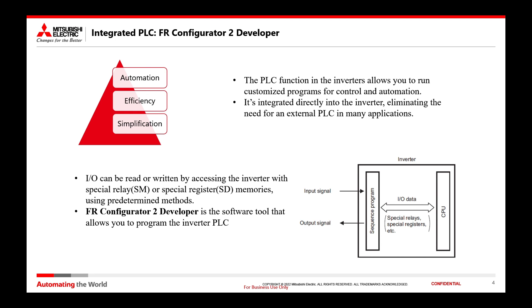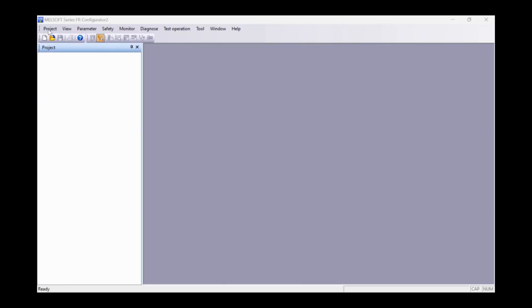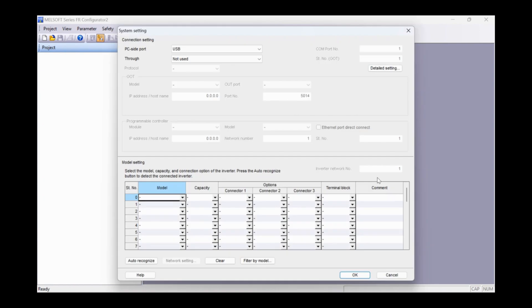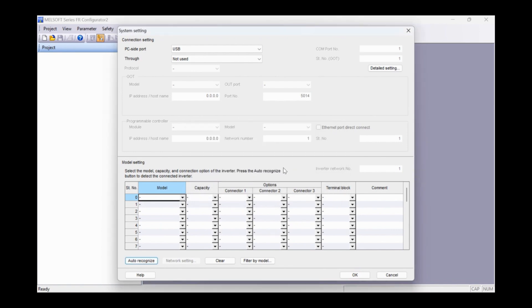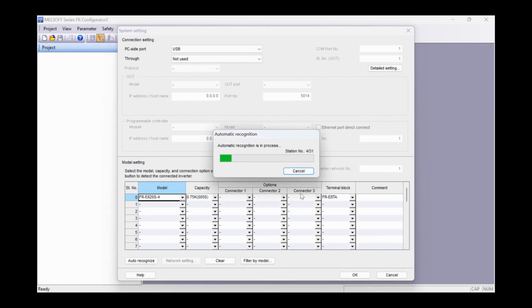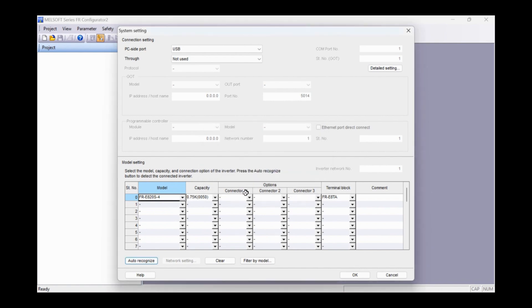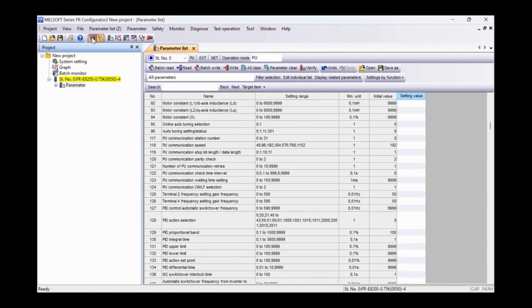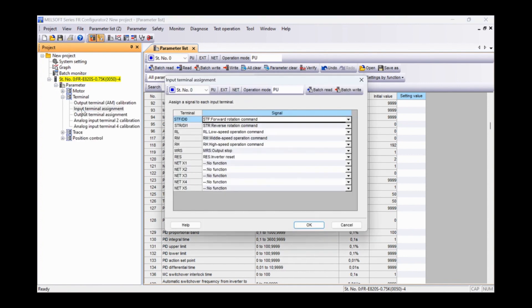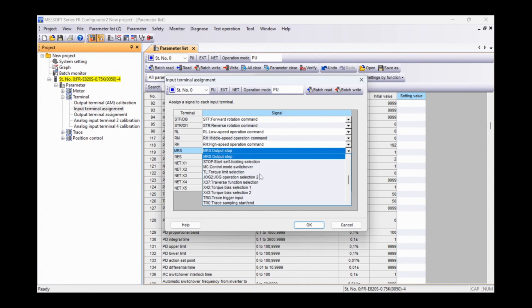But first, let's see how to activate this functionality of the PLC starting from an empty project. So let's start by opening a new project. I am connected to the inverter by USB and proceed by performing automatic recognition. We can end the search as the device has already been found. Let's go online and the first fundamental operation that we must perform is to set the sequence start bit SQ in one of the physical inputs present in the terminal block, with the relative electrical connection.